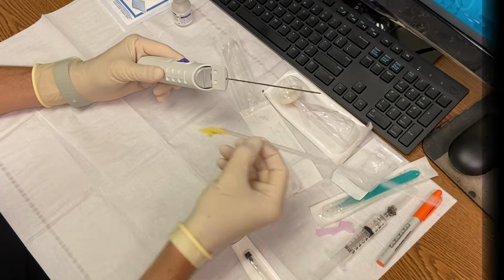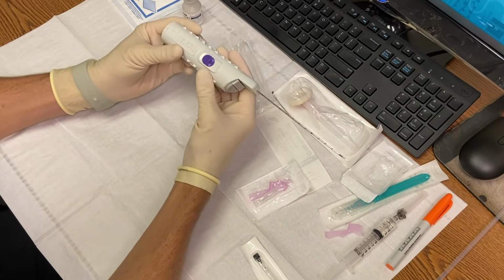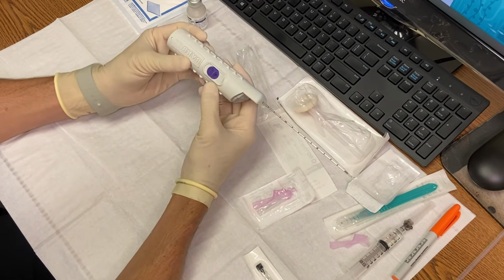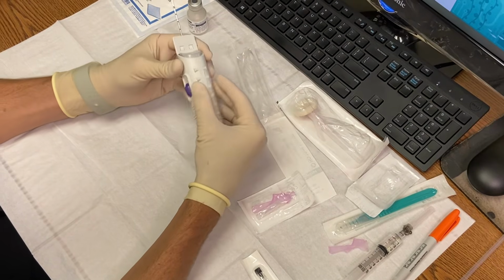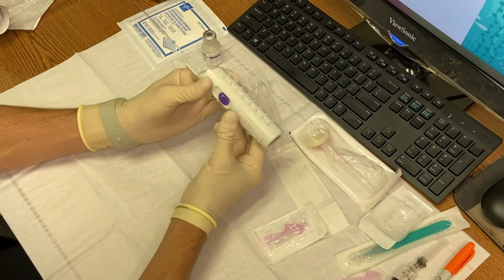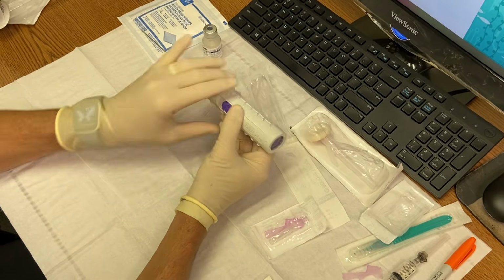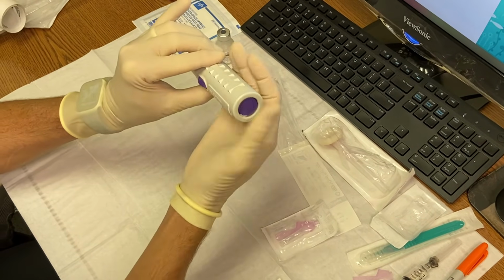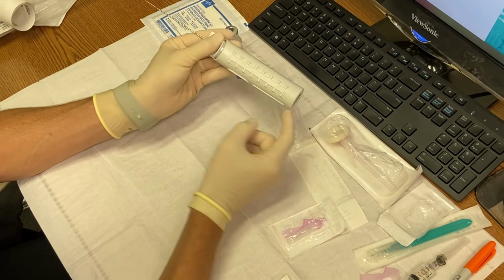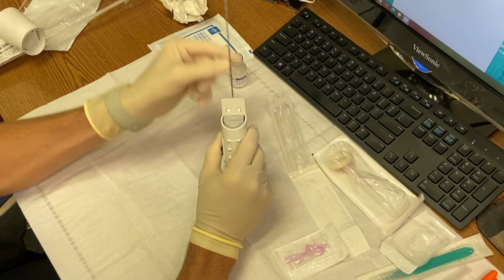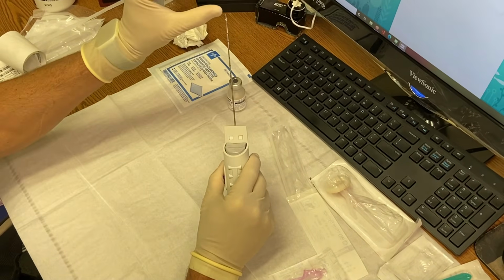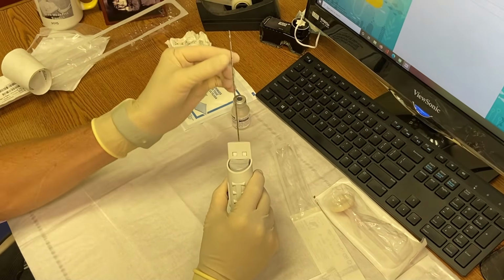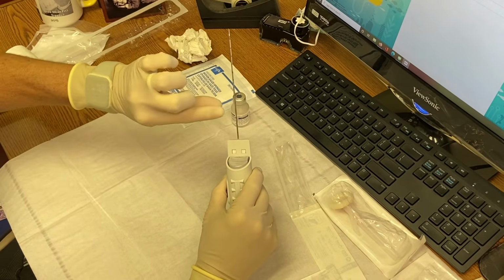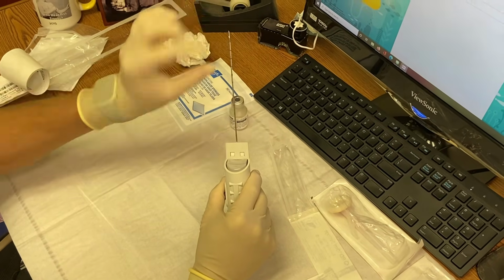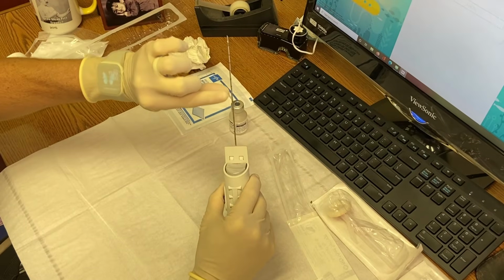We'll pause here to review do's and don'ts of the biopsy needle. After this is removed, you can discard it in the garbage, and your needle, once there's 2 buttons pressed, is spring-loaded and ready to fire. The 2 mechanisms to release the needle are this button, which you would push this way, or the button on top, which you can just depress there. What depressing this or this will do is allow the spring on the inside to shoot the needle about that much out. It'll shoot out the hollow part, and after the hollow part has captured the tissue in the middle, the sheath on the outer part will cover it.